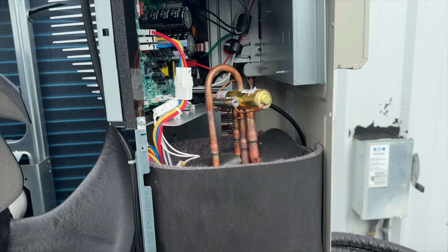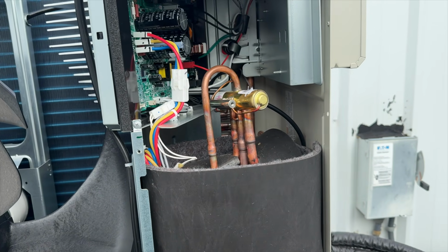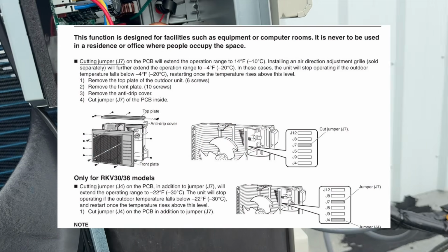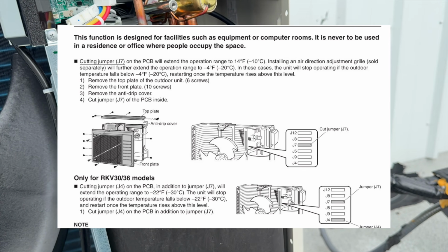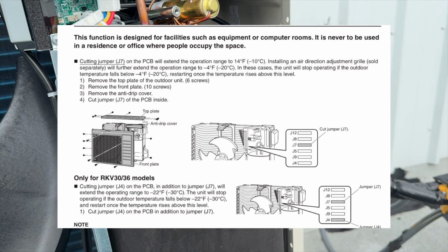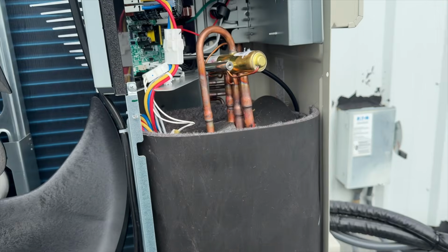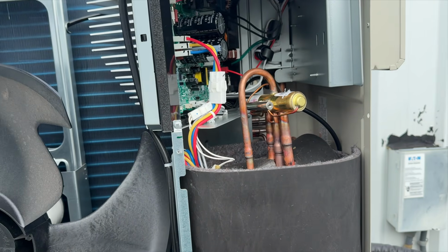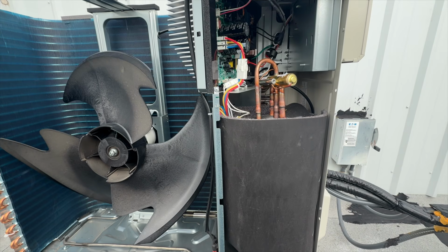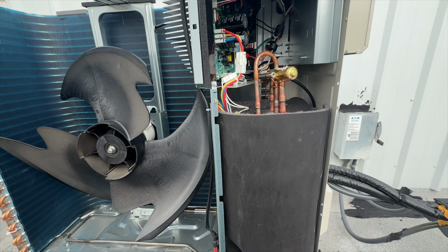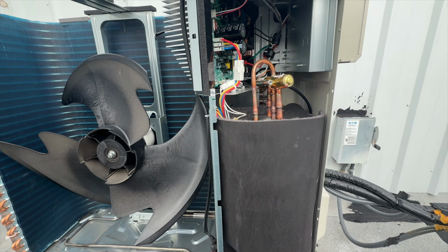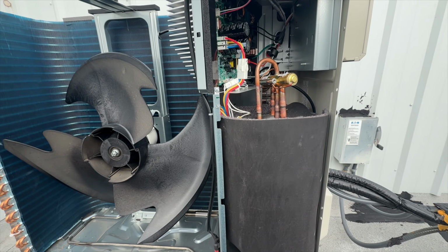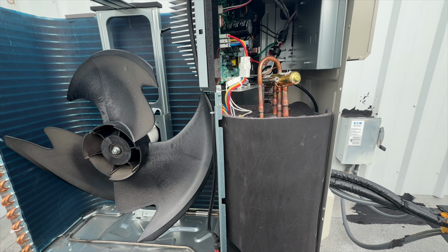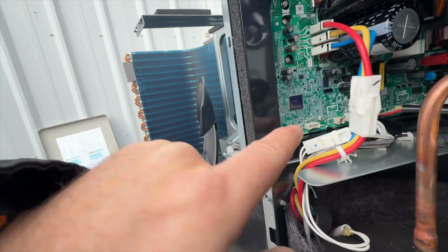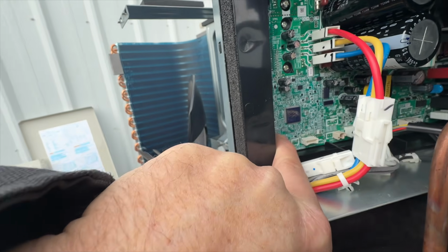All right, so if we're looking at our install manual here, you can see it says cutting jumper 7 on the PCB will extend the operational range to 14 degrees. So right now it's basically locked out because it's below 50. And by adding the wind baffle, that'll get us down to -4. So we have the wind baffle, so it looks like the jumper didn't get cut, and that's gonna be J7. So do we have J7? Yeah, it's not cut, so we need to cut that.